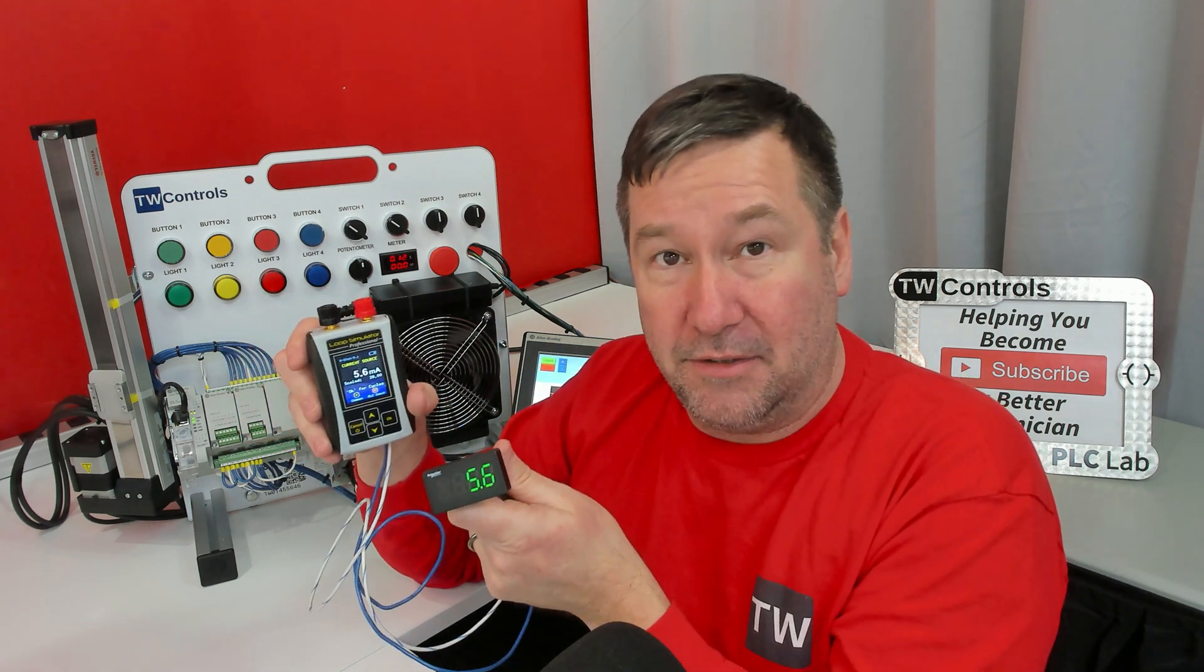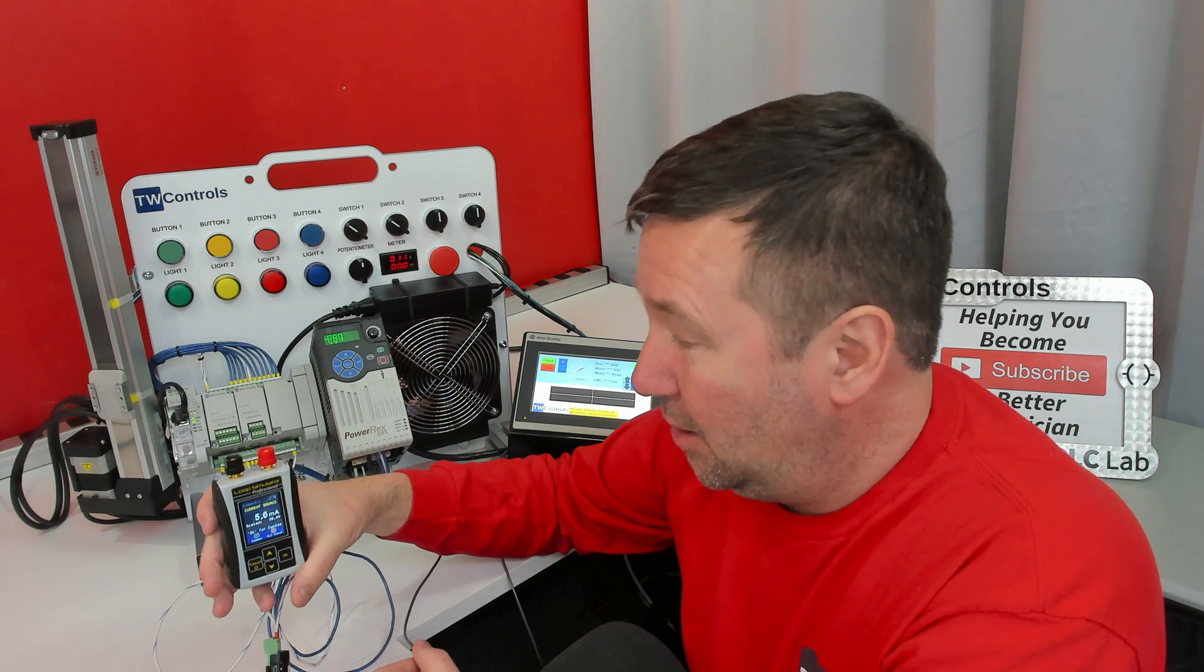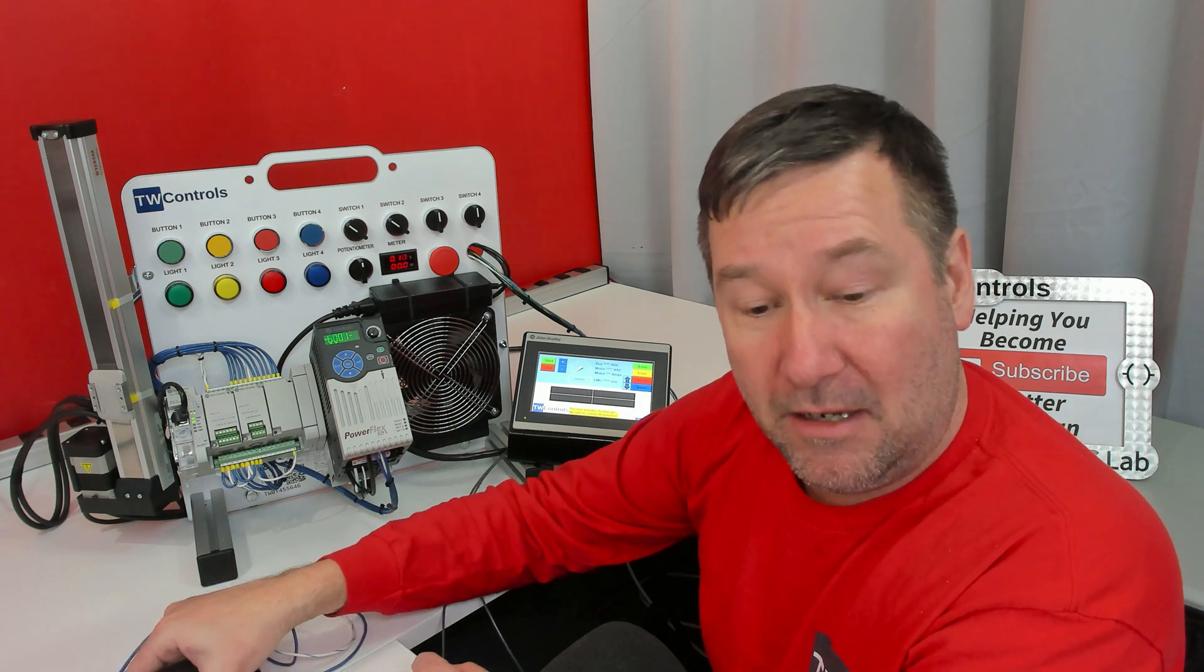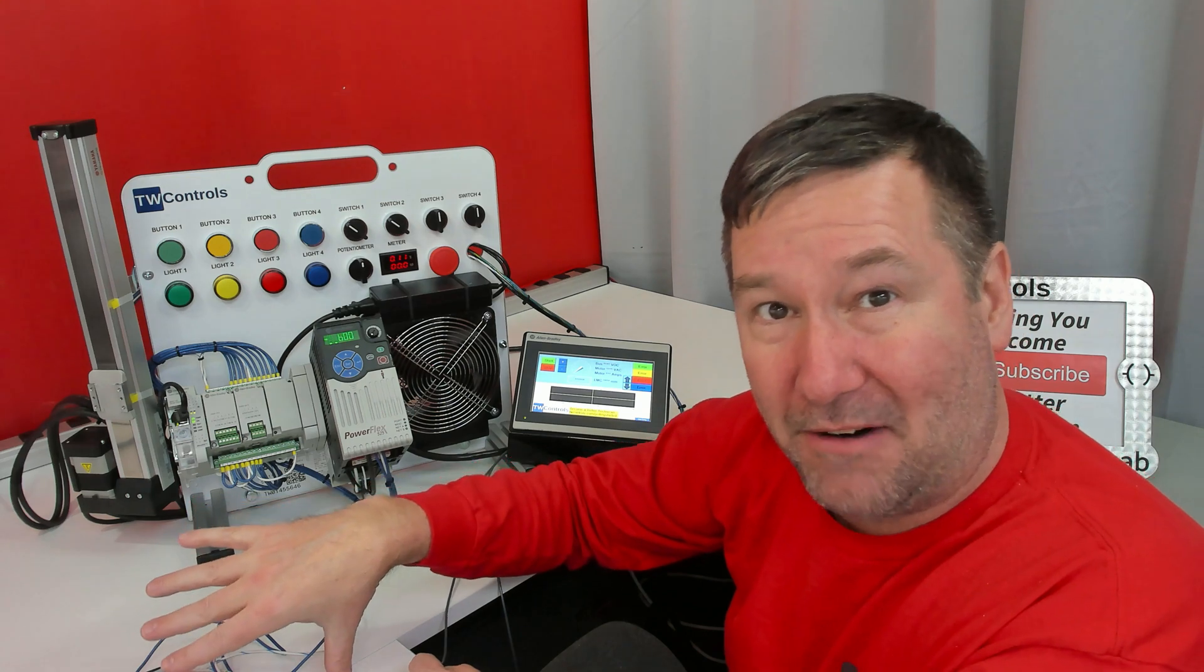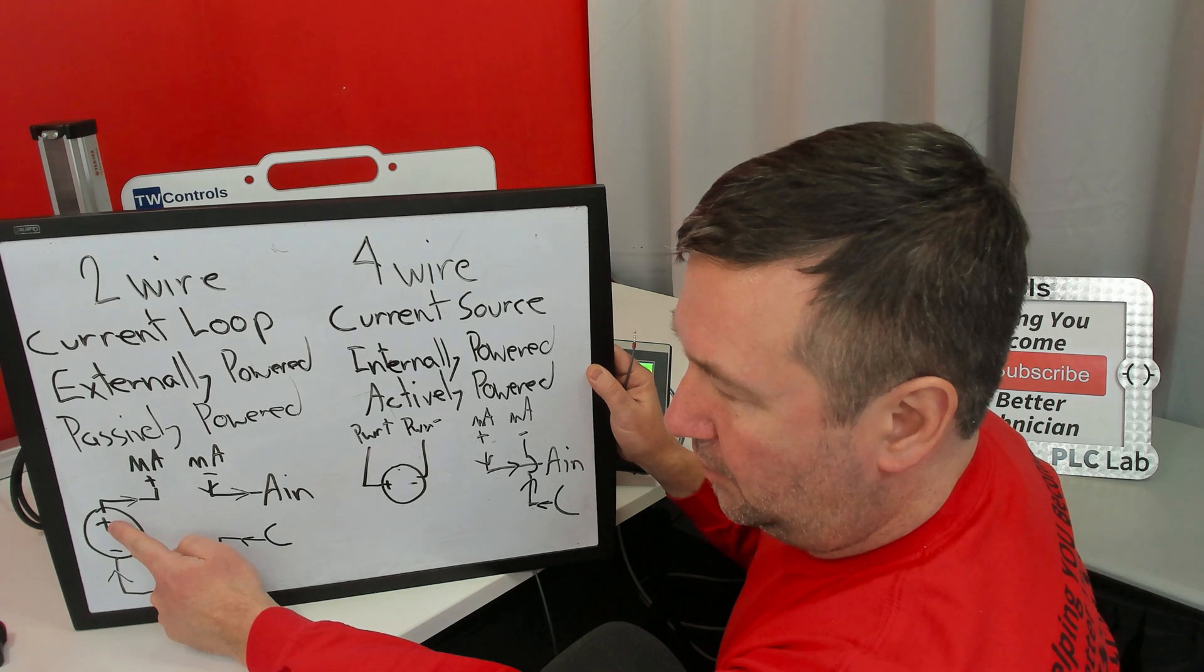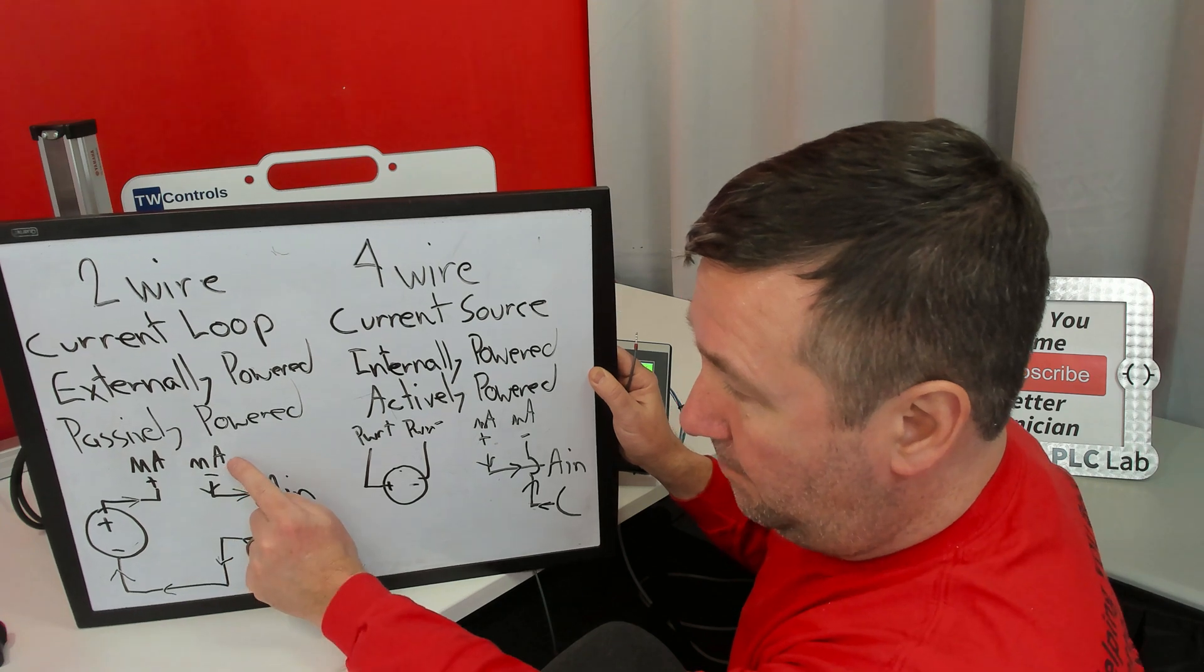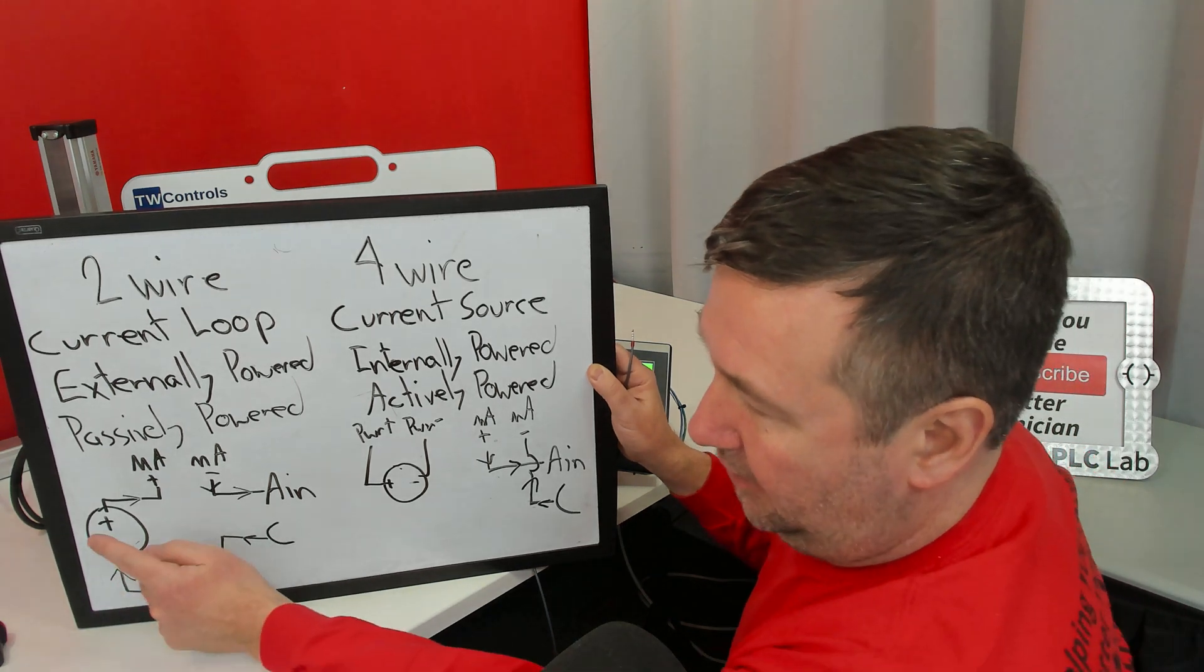All right, now let's do the opposite. I'm going to run the analog simulator in current source mode. But I am going to wire it for a two-wire connection. That way, we have our PLC trainer's power supply and the external power supply in the same loop. To do that, we're going to take the plus 24 volt to our milliamp plus. And then we're going to take the minus milliamp over to our analog in. And then we're going to take the common back.